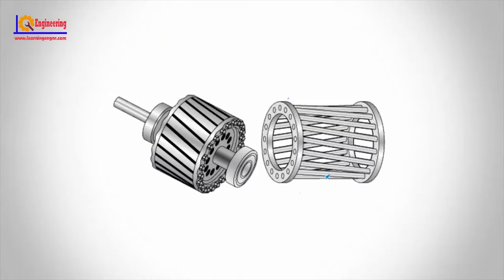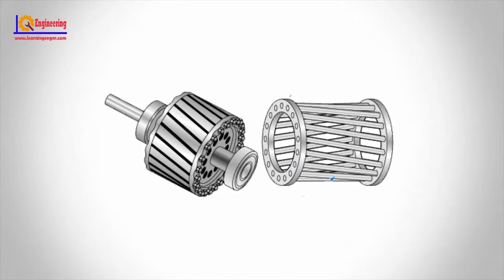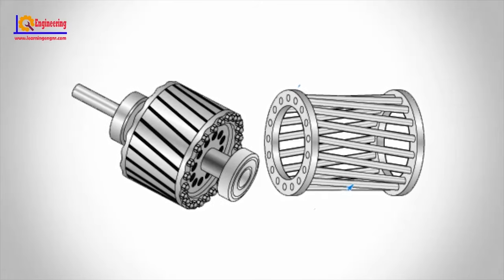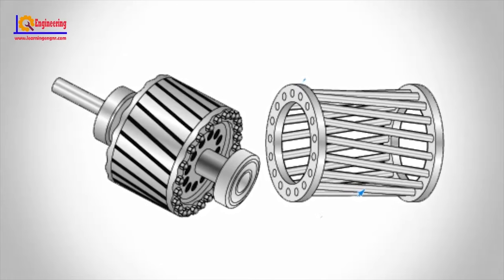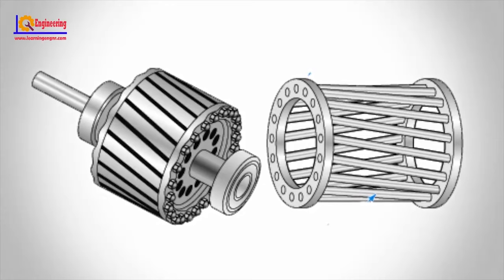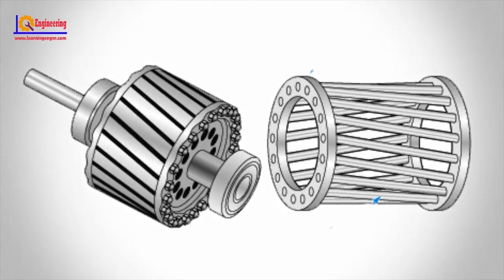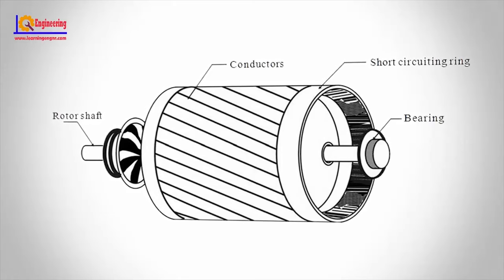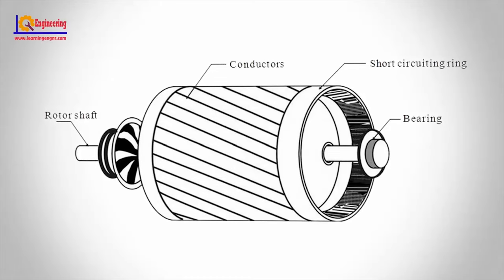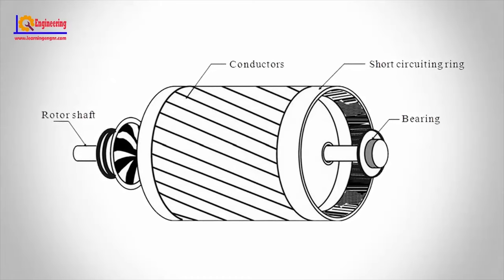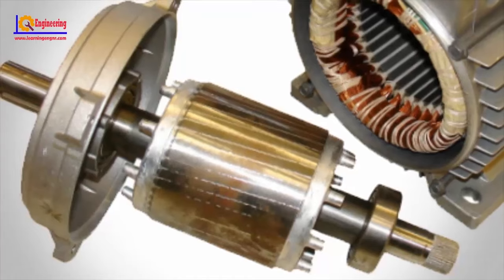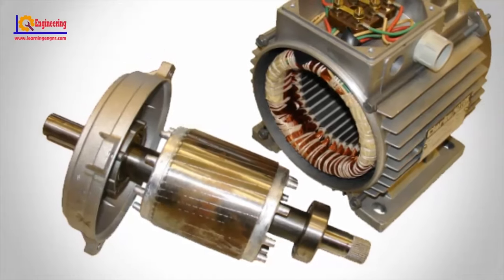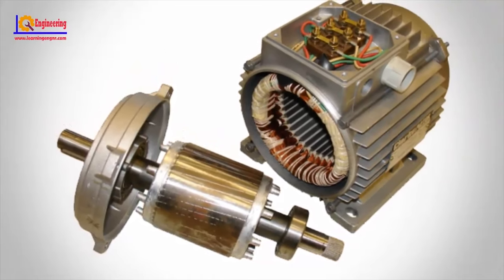The squirrel cage rotor consists of laminated steel in the core with evenly spaced bars of copper or aluminium, placed axially around the periphery, permanently shorted at the ends by the end rings. This simple and rugged construction makes it the favorite for most applications. The bars are slanted or skewed to reduce magnetic hum and slot harmonics and to reduce the tendency of locking. Housed in the stator, the rotor and stator teeth can lock when they are in equal number and the magnets position themselves equally apart, opposing rotation in both directions.